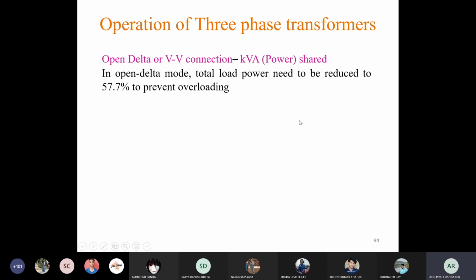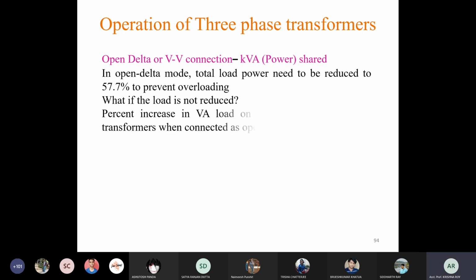So now, in open delta mode, total load power needs to be reduced to 57.7% to prevent overloading. Now, what if the load is not reduced? The simple answer is that the transformer will get damaged. But here we want to calculate how much overloading will occur in percentage. So let us see.